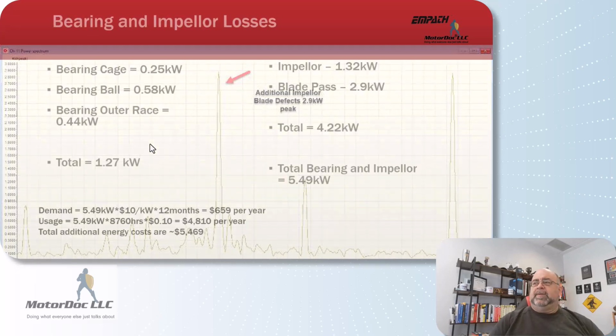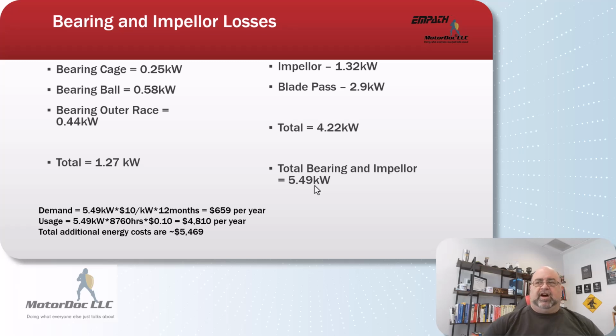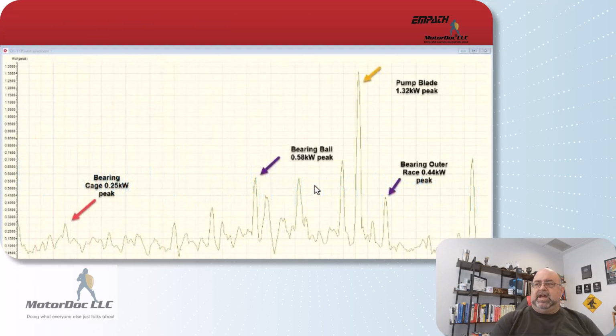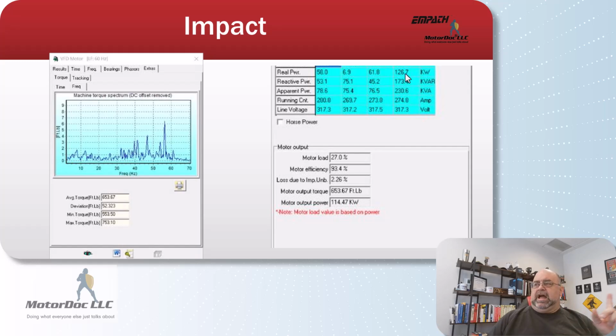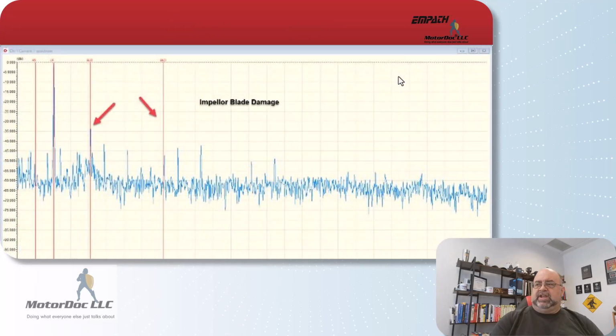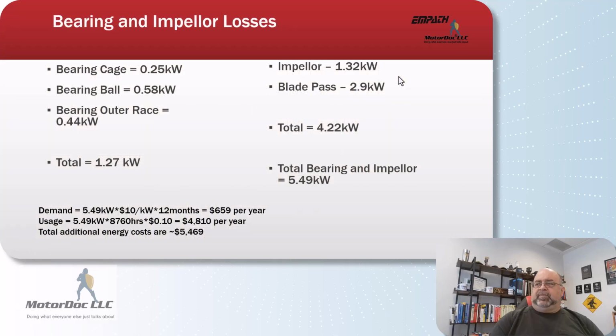So between the bearings and this, I end up with a total of 5.5 kilowatts of the actual load, which was, I believe, let's go back to that. The actual load at the leads going into the motor is 126 or 127 kilowatts effectively. So this blade and bearing comes out to be 5.49 divided by 128, about 4.3% of the total load. So that comes out to be $5,500 per year, roughly, in additional cost to provide the energy necessary to feed these defects.